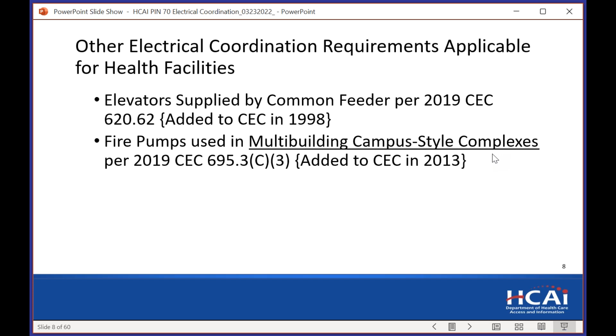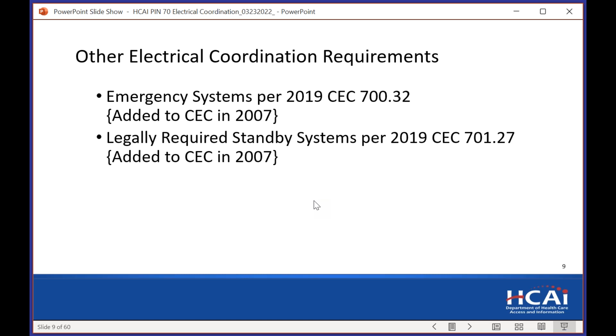We have two other requirements for coordination that we'll talk about, and that is the emergency system and legally required standby systems in Articles 700 and 701. These are not used in hospitals. They're in the code in case you're feeding a non-healthcare building from a campus and are required to have an emergency system for that building, but they are not applicable to a hospital or SNF.